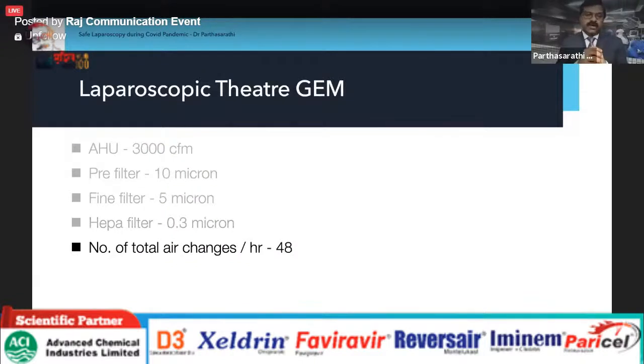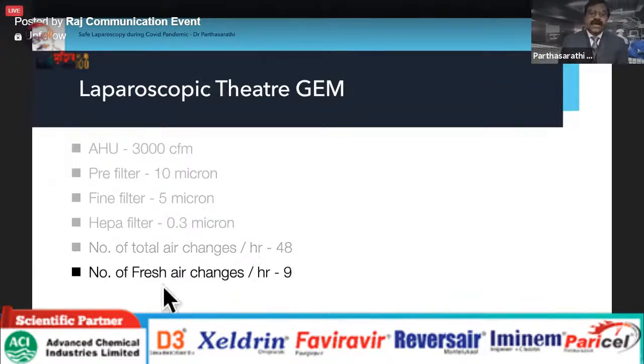So what are the other protocols? The number of air changes should be 40, that means 40 per hour. In the entire 20 by 20 OT room, the air should cycle. It will come in laminar flow in the center of the OT, and the outlets will be at all the corners. So the number of cycles should be a minimum of 40. I calculated that our OT has 48 cycles per hour.